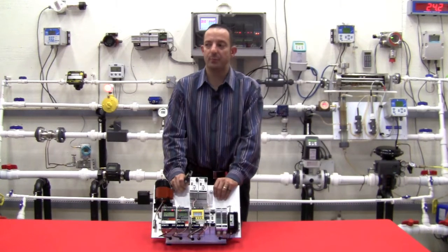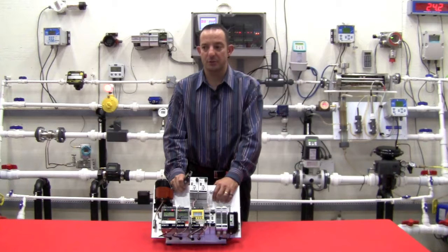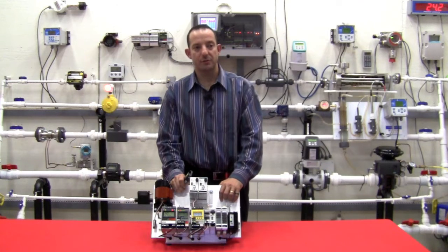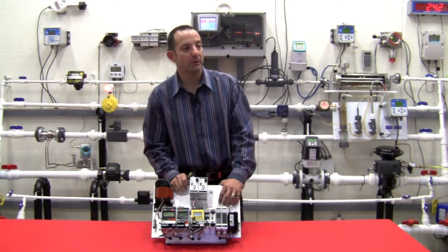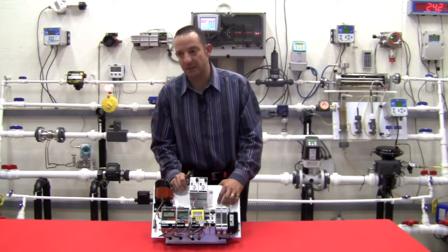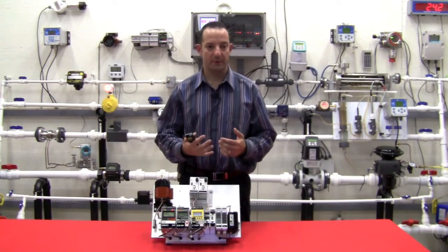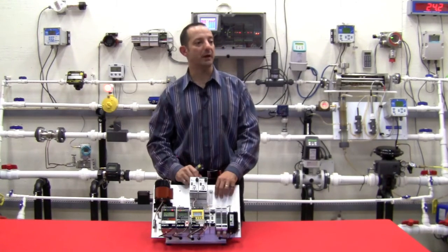For example, if you put 3 or 4 loop indicators in a current loop and a pressure transmitter, you might run the voltage drop across all those devices up close to or in excess of the 24 volt supply of the loop. And so what the isolator does is it allows you to take some of those devices off of that primary loop and set up a secondary loop whose output is driven by that isolator.